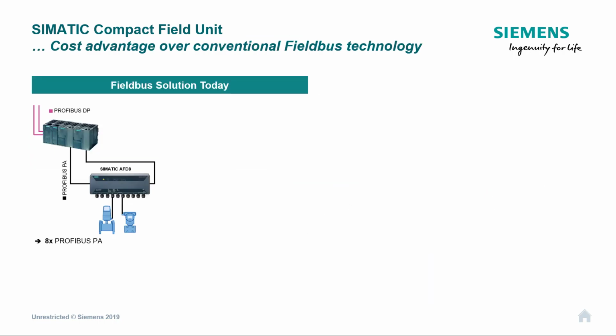So if we have a look at the old solution, which is still currently available, sorry, I shouldn't have called it old, we're using our DP to PA couplers on a redundant ring, and to do that we need to use the active backplane, and then we're coming out to an AFD with 8 channels. So this is the box in the field, and this box here, this DIN rail arrangement, has to sit in a cabinet somewhere in a safe area.